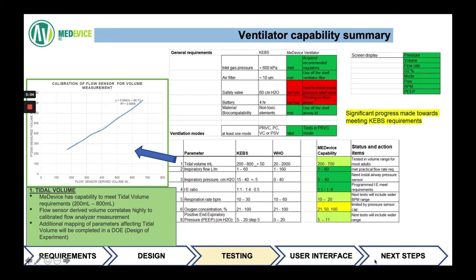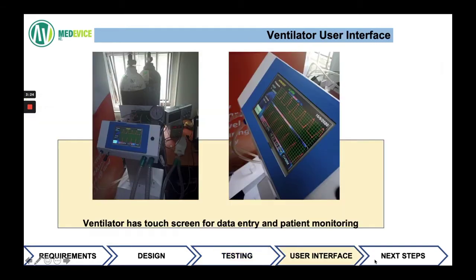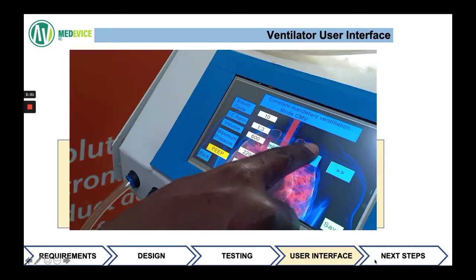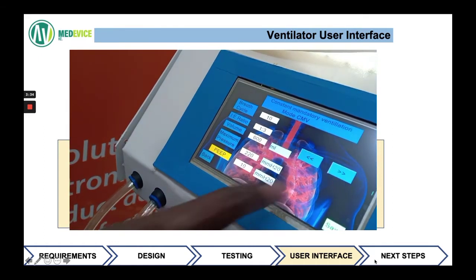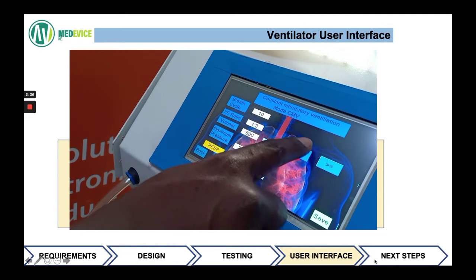Our respiration rate is 10 to 30 breaths per minute, and we have a positive end expiratory pressure, or PEEP, of between 5 and 20 centimeters of water. We are able to have oxygen concentration between 21 and 100%. We're still working on our mixing capability.